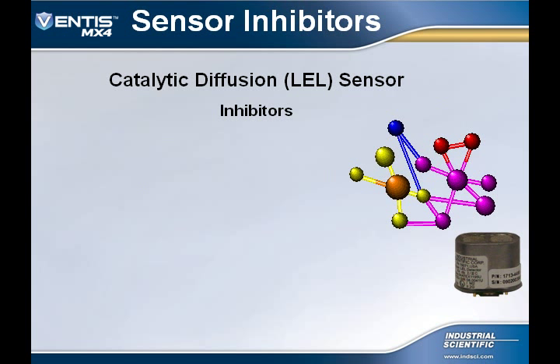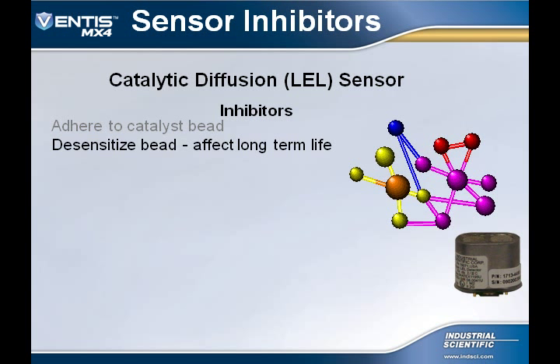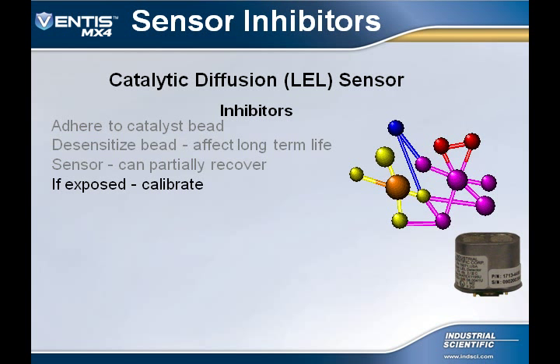Another caution with the LEL sensor is exposure to inhibitors. Inhibitors also adhere to the catalyst bead. They actually affect the long-term life of the sensor. The sensor can partially recover, but the damage may have already been done if exposed. If you feel that the sensor has been exposed to an inhibitor, a calibration should be accomplished. As I said before, inhibitors affect the long-term life of the sensor, which means instead of lasting 3 years, the sensor may only last 1 to 2 years.